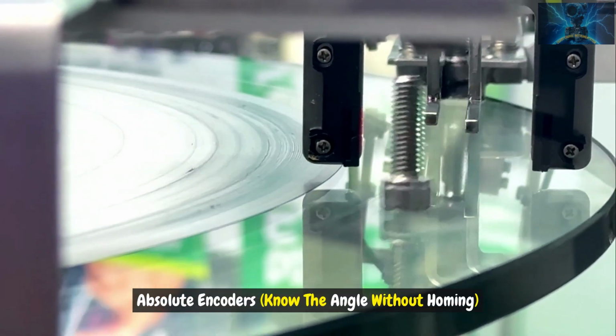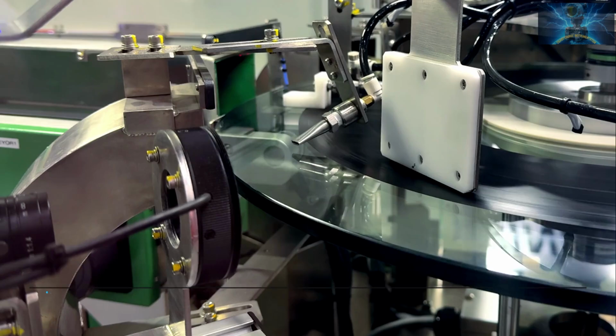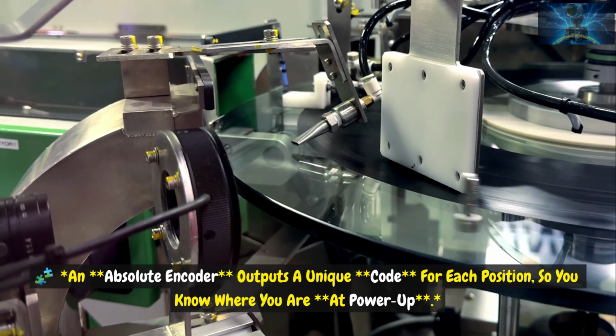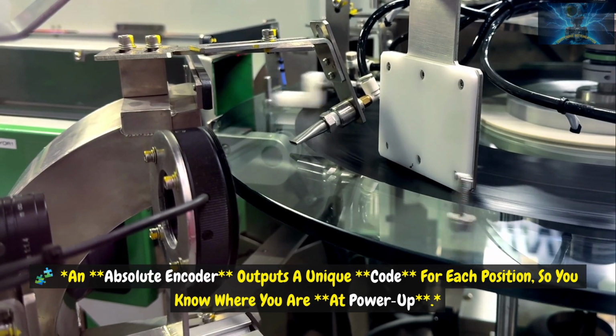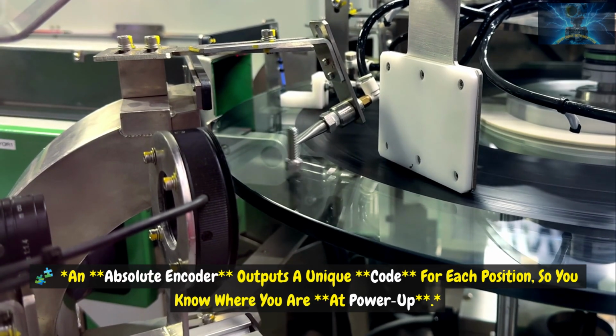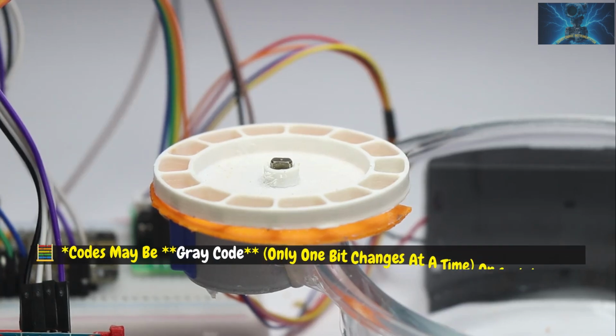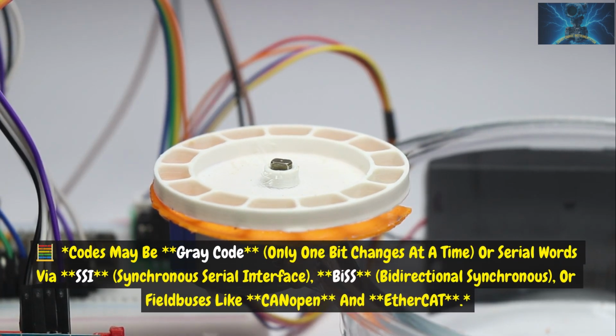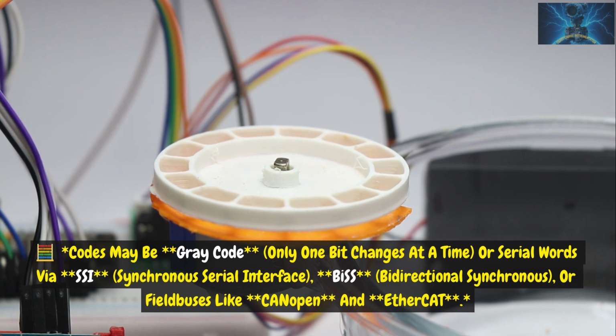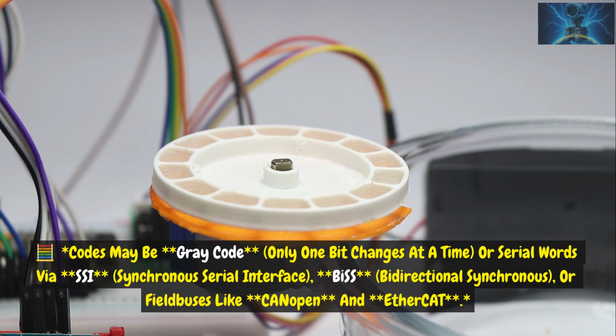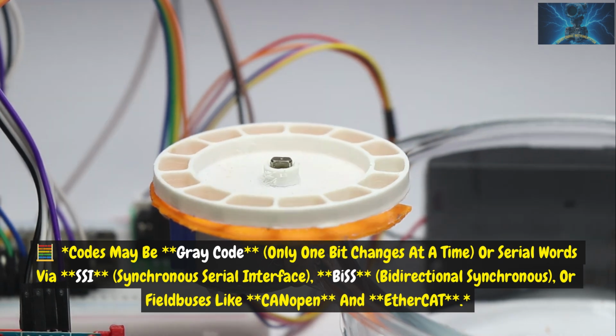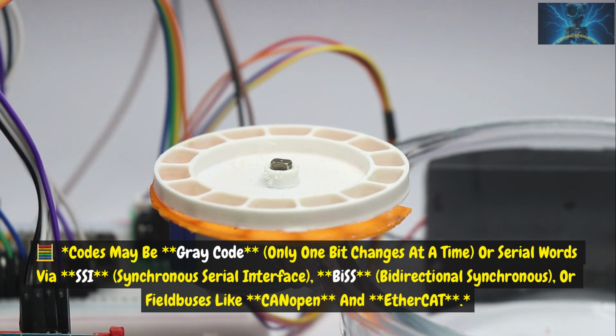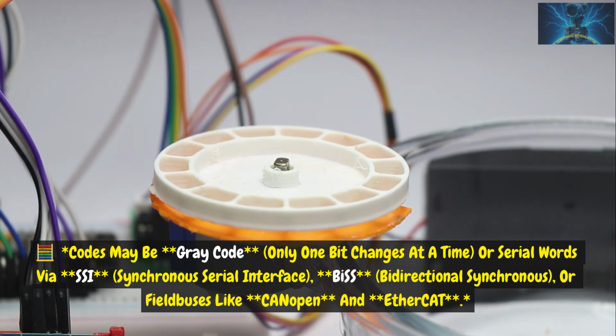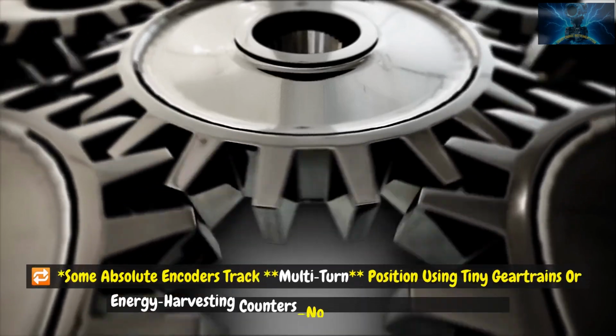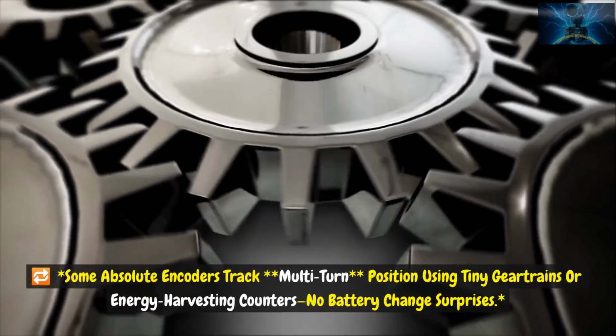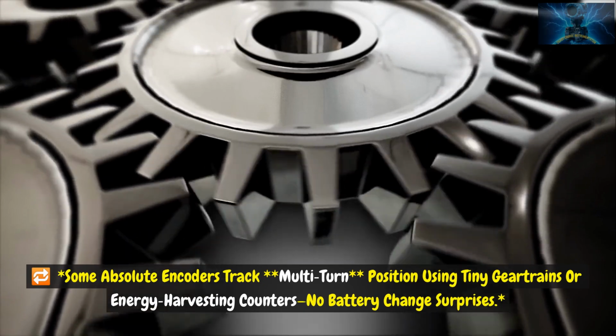Absolute encoders know the angle without homing. An absolute encoder outputs a unique code for each position, so you know where you are at power up. Codes may be Gray code, where only one bit changes at a time, or serial words via SSI, synchronous serial interface, BiSS, bidirectional synchronous, or fieldbuses like CANopen and EtherCAT. Some absolute encoders track multi-turn position using tiny gear trains or energy harvesting counters.